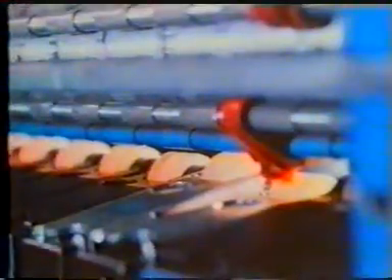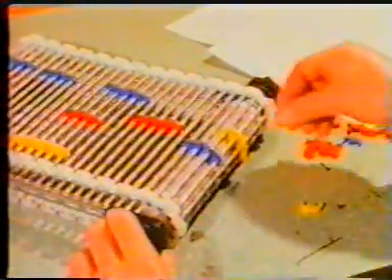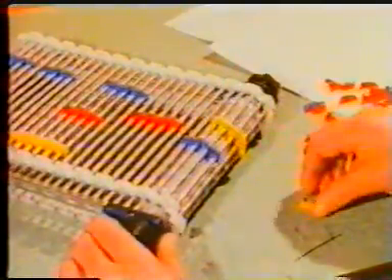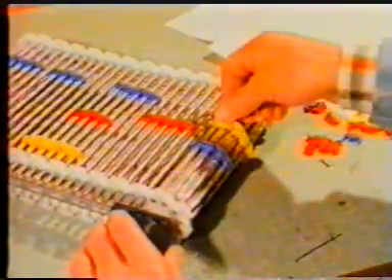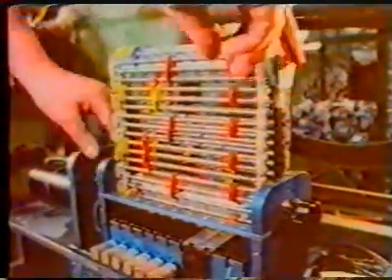With the cam belt, information for providing the signals is given by cam. The cams are attached to correspond to the program sequence. The program duration is determined by belt length and rotational speed. Small modifications to the program are made by reattaching the cams on the machine, whereas larger program modifications are accomplished by replacing the complete belt.